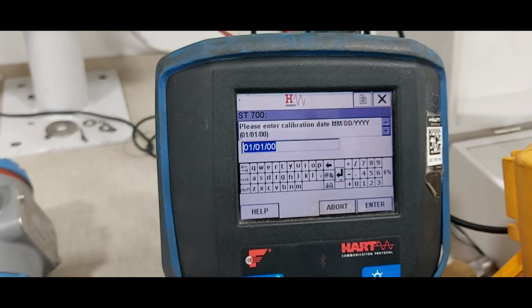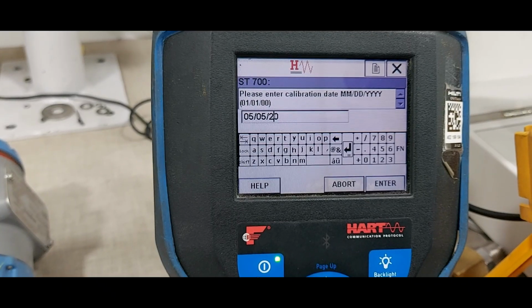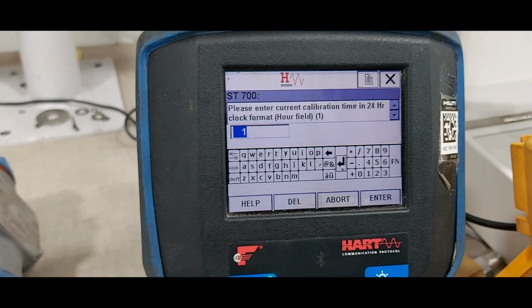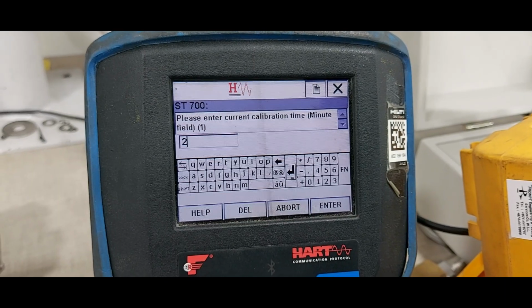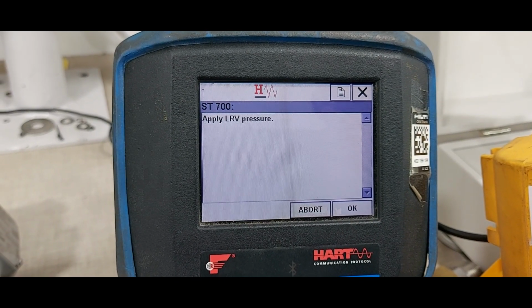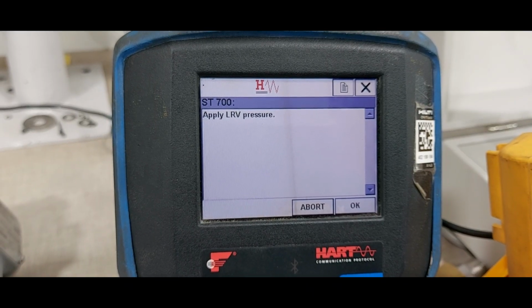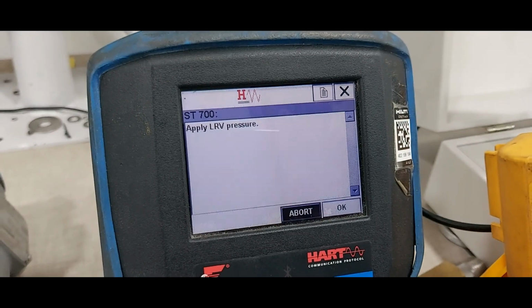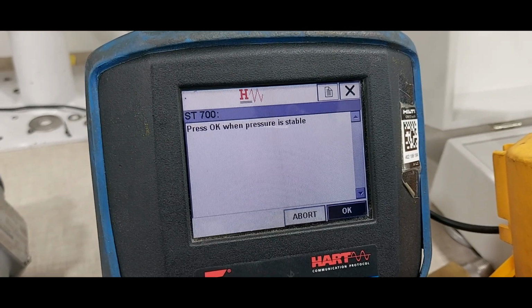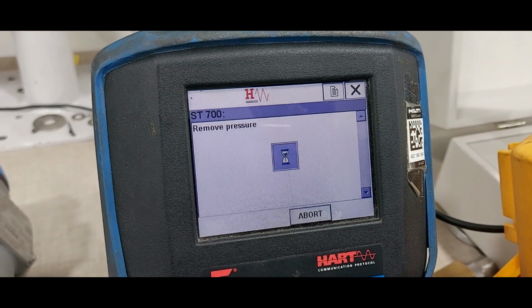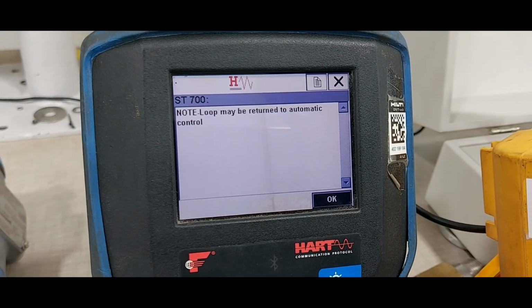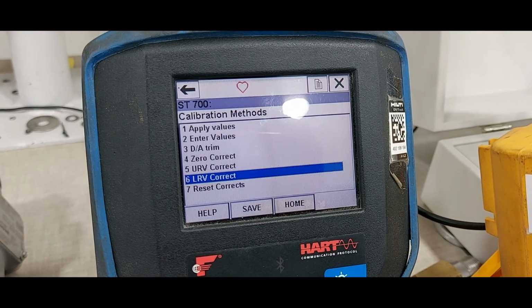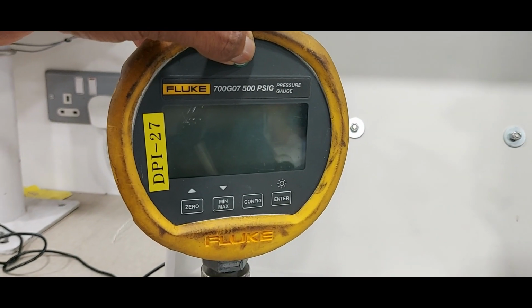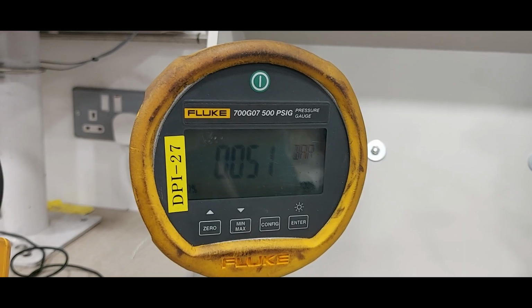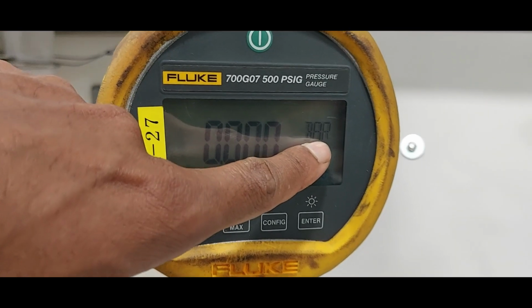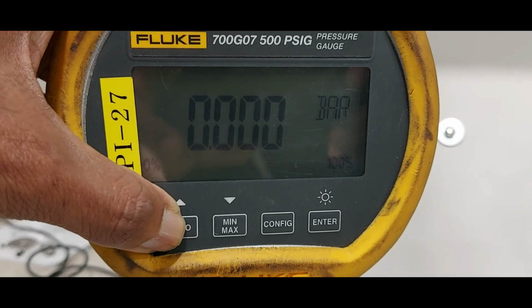Enter the date, 5/5/2025, at 12 o'clock, okay. Apply the LRV pressure. LRV pressure now is 0 condition. Press OK. Then automatic control is OK. Next, power on the reference gauge. Select the unit. Unit is bar. Set the 0.